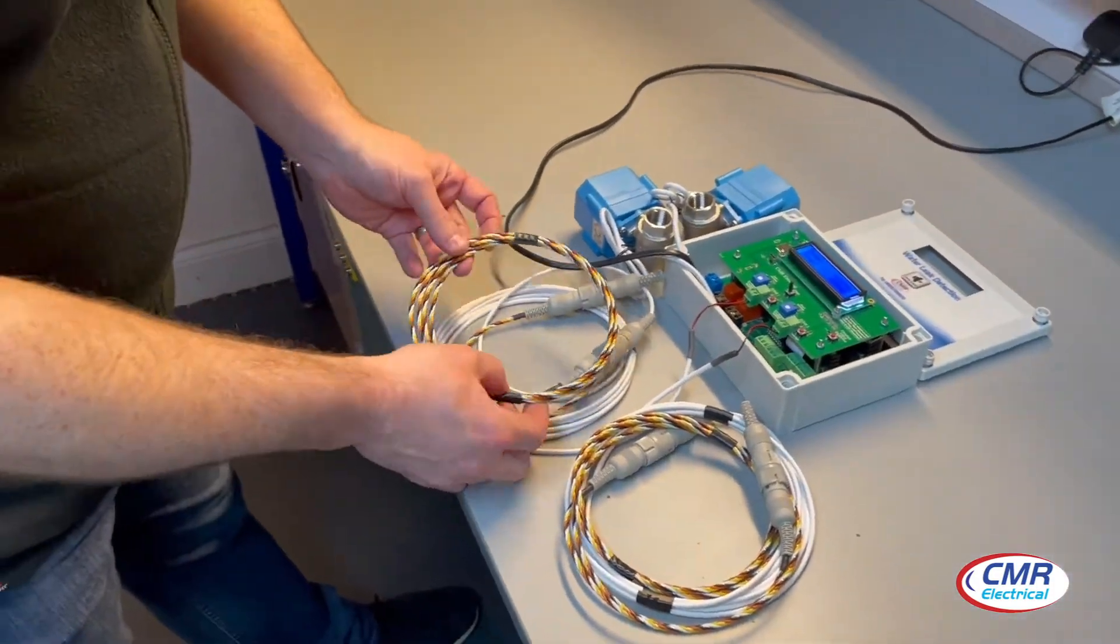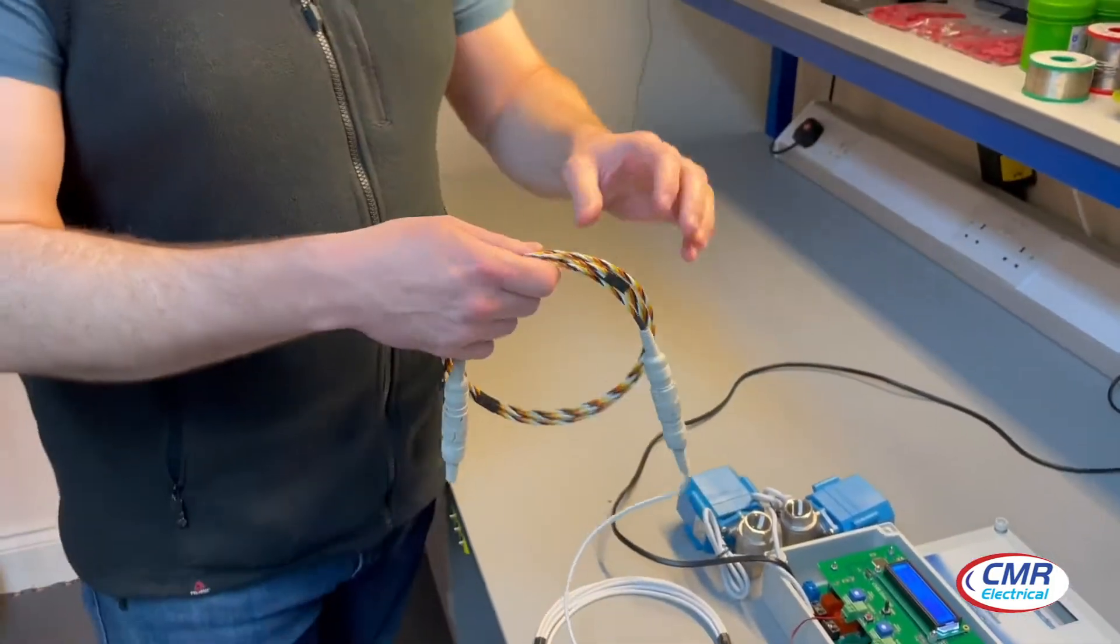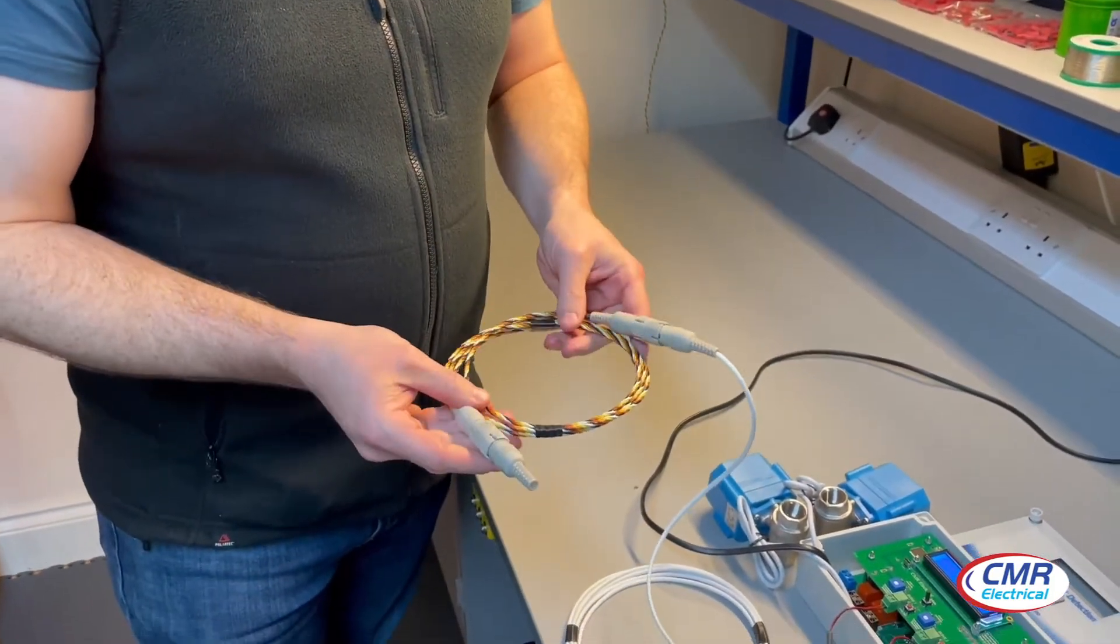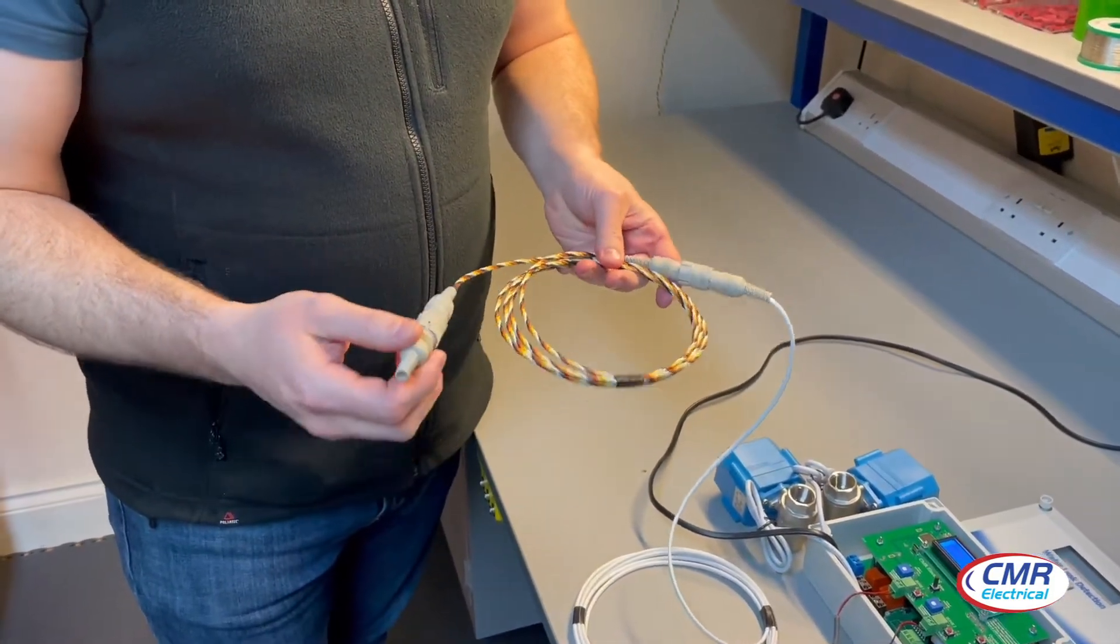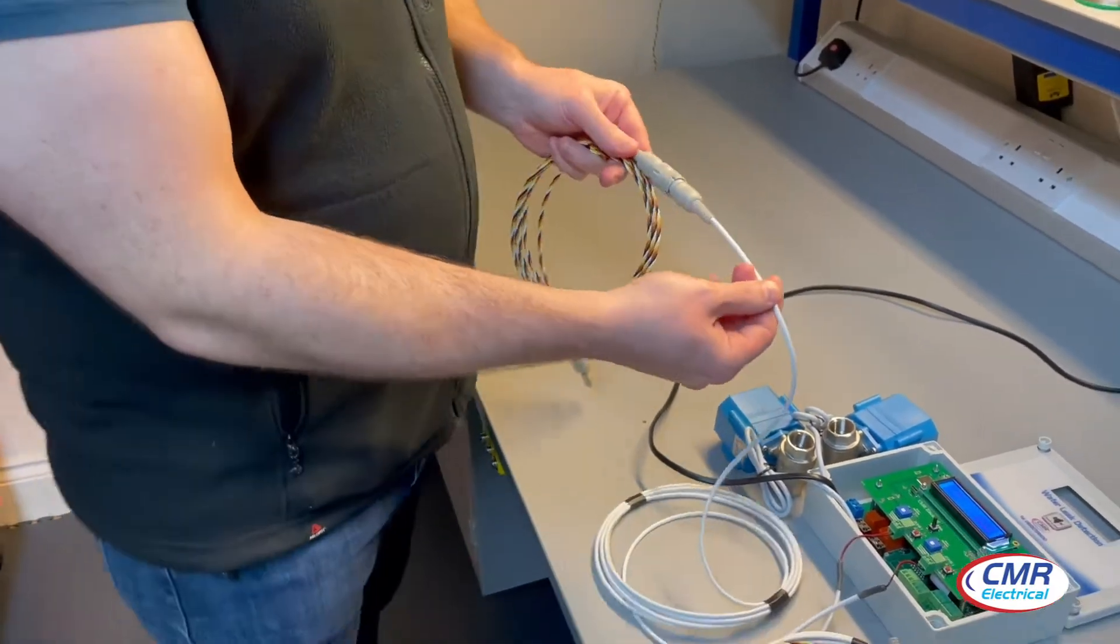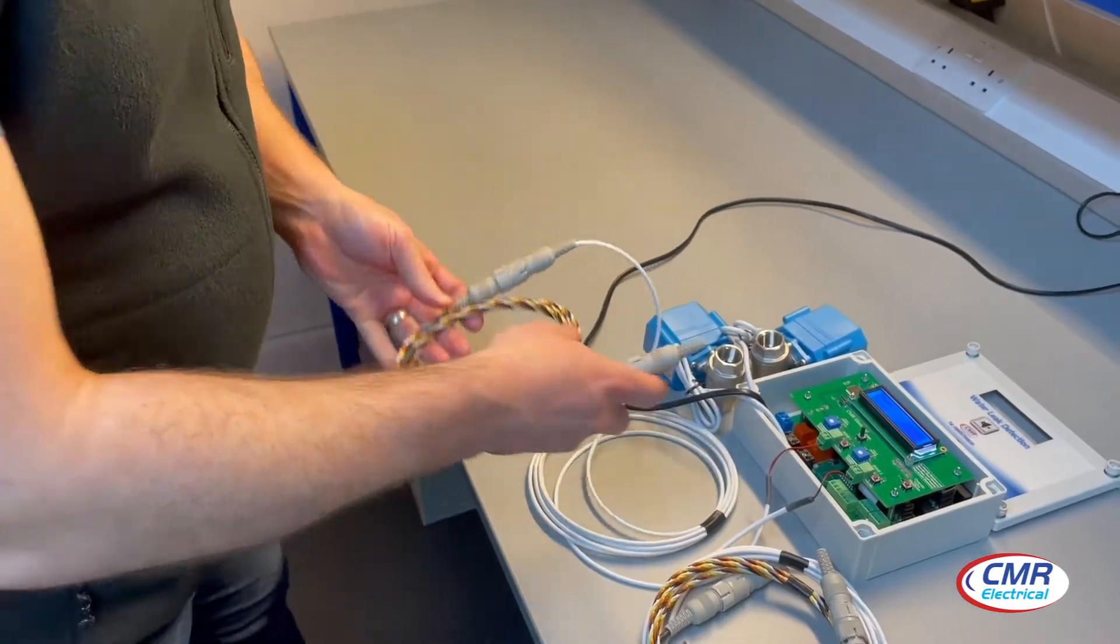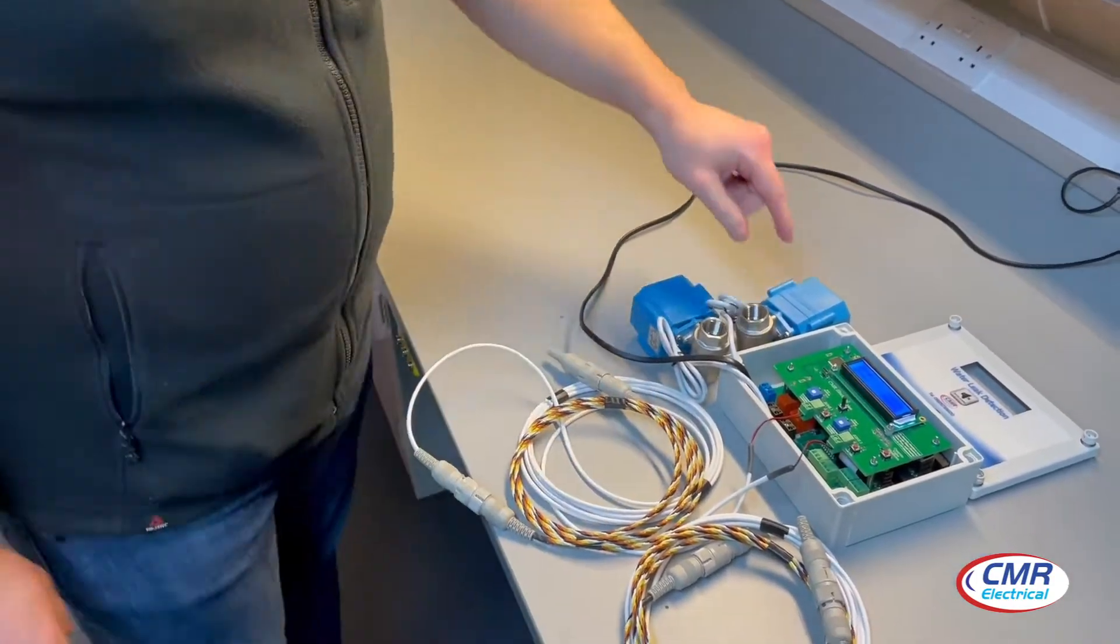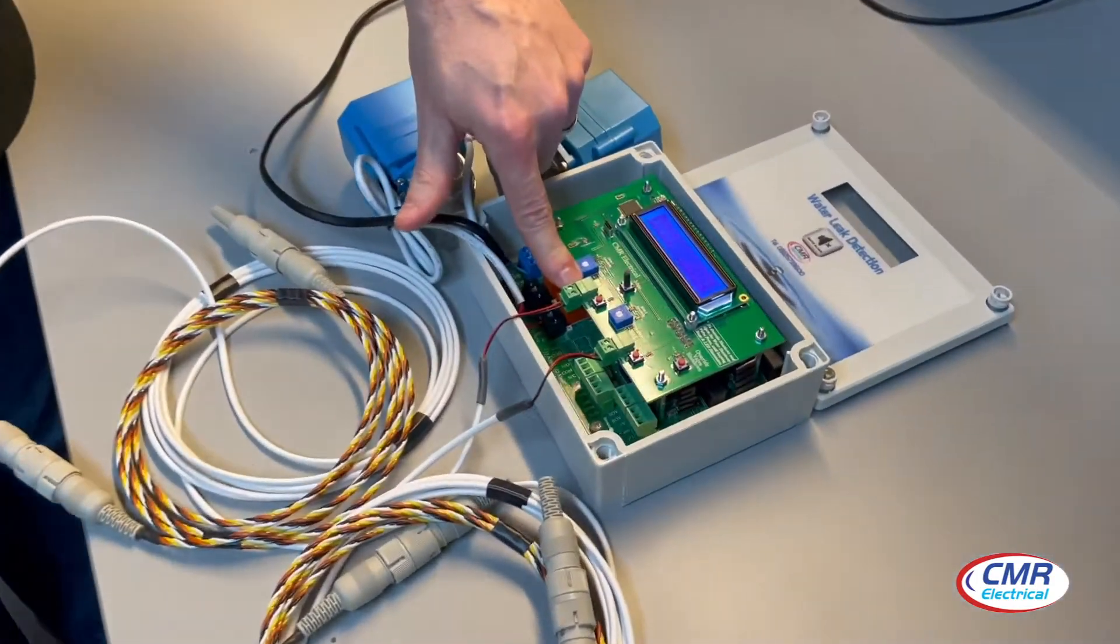We'll start off with the detection cables. This is a detection cable. It's a four-core multi-colored leak detection cable. It has an end of line which plugs from the end of here and connects to a white signal cable, which is a two-core signal cable that connects into a two-way terminal block here.